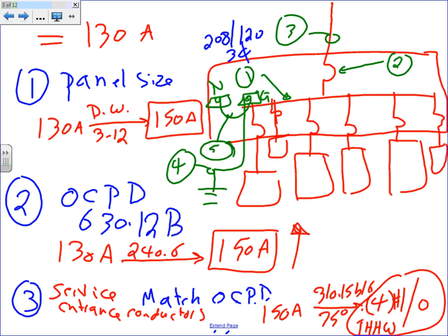Chris, what do you come up with? Schedule 80. These have 20% expansion. I have how many conductors? I have 1/0 AWG wire size. How many conductors do I have? 4. THH, I don't have THHW up here. And conduit size, 2 inch. Did you say 2 inch? Yeah. Yep, came up 2 inch.